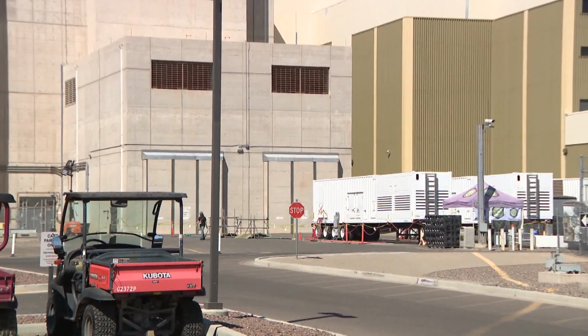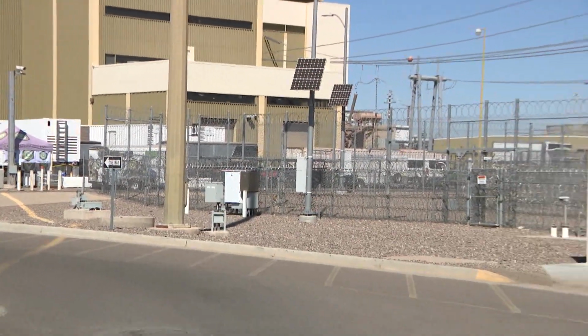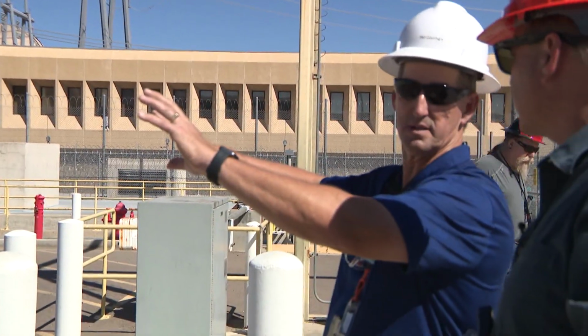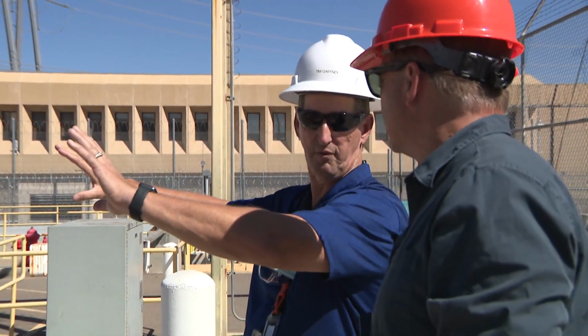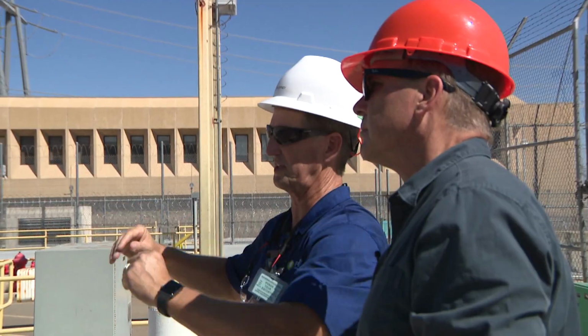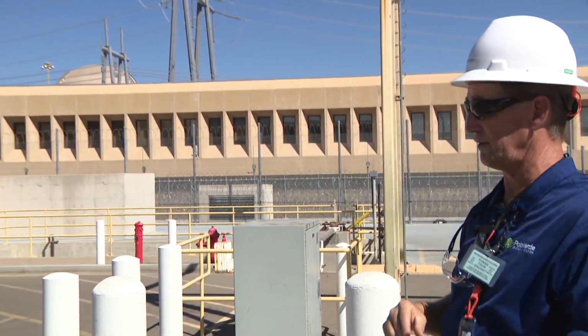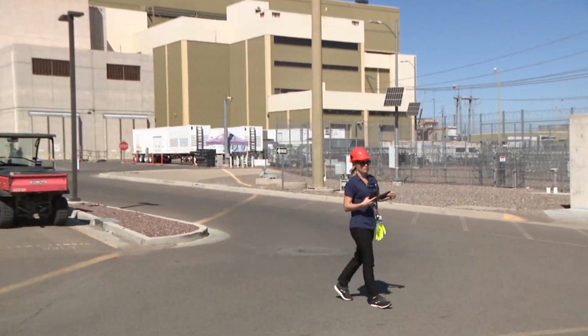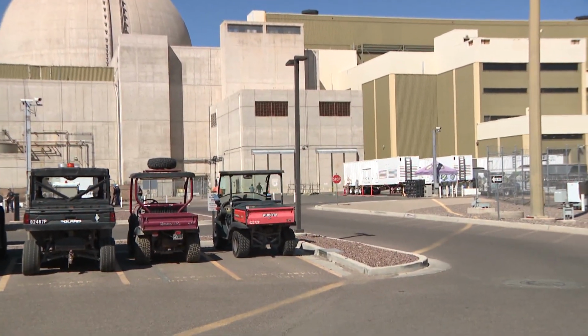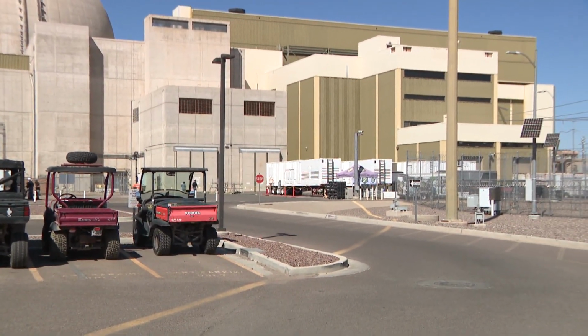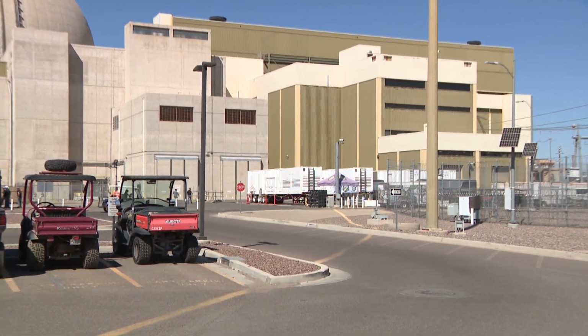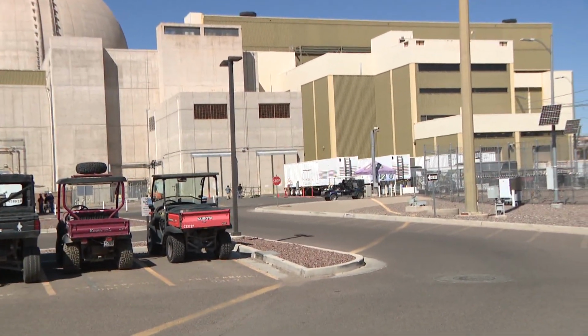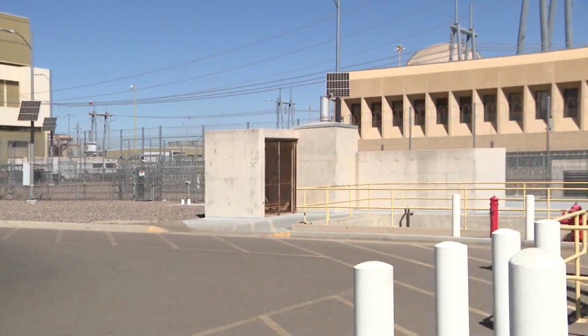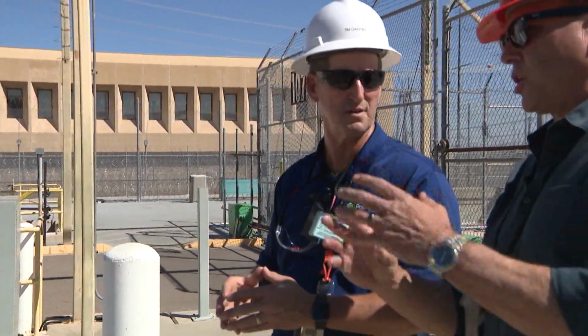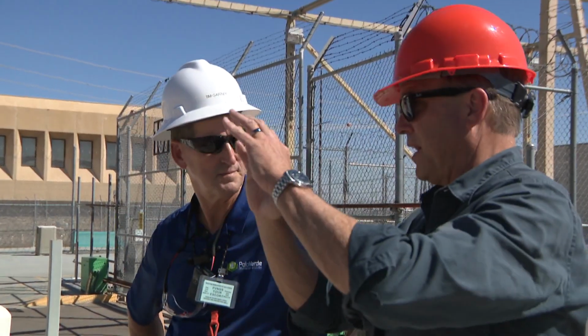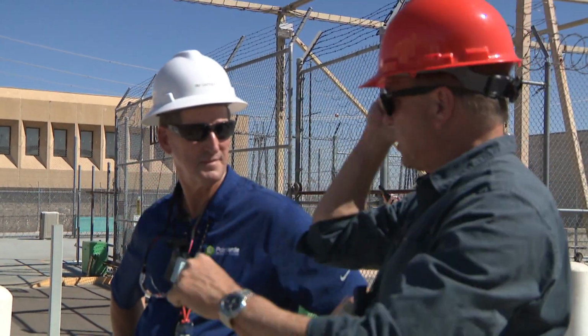Like we talked about in the switchyard, we use off-site power going to our safety buses. At all times it's ready to provide power to our safety systems, safety pumps, etc. The diesel generators, if we have a loss of that power, will instantly light off. Within 10 seconds they'll get up and load, providing 4,000 volts and 5.5 megawatts of power to the systems necessary to hold us in safe shutdown.